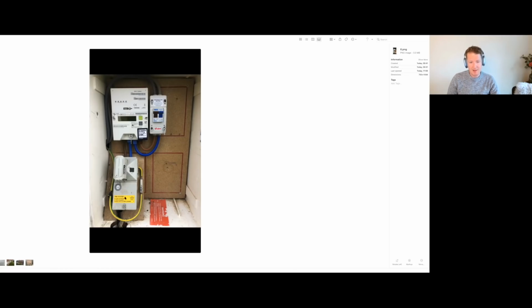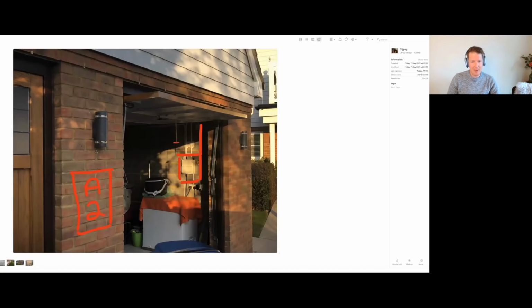Obviously it's a PME system as well, so we'll need to install the charging point that has built-in PEN fault detection, or we'll have to install a separate PEN fault detection device, which we don't have space for, or we'll have to install an earth electrode, which is not recommended. So really we're narrowing it down now, and the Andersen A2 is probably out of the picture.